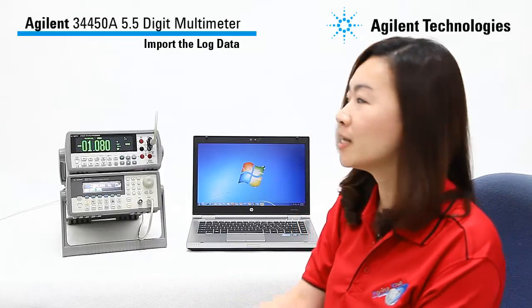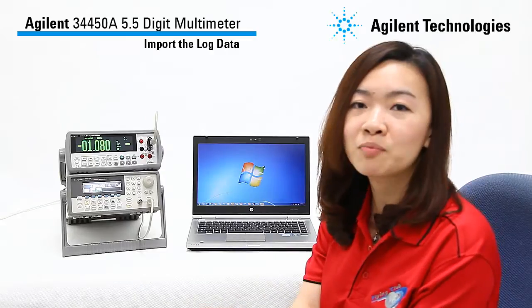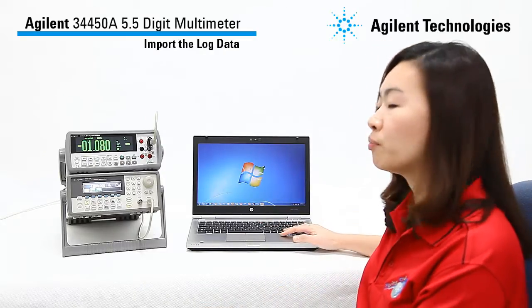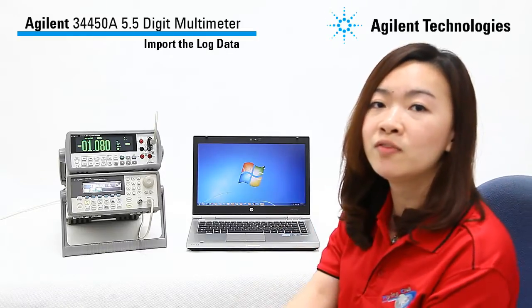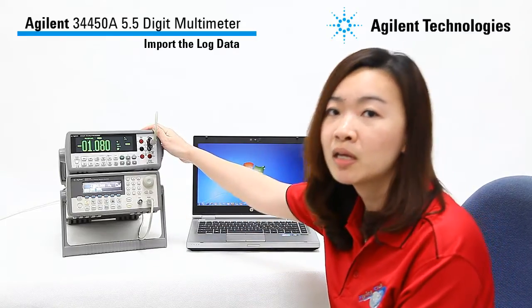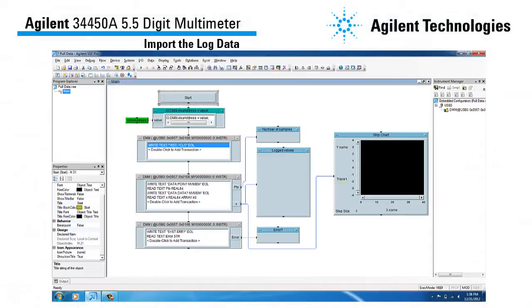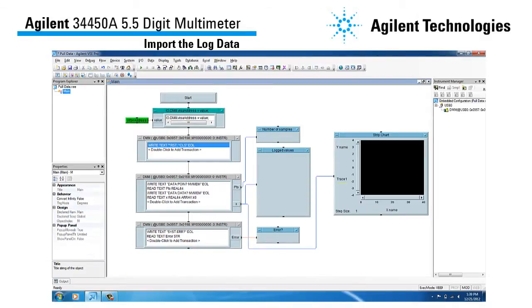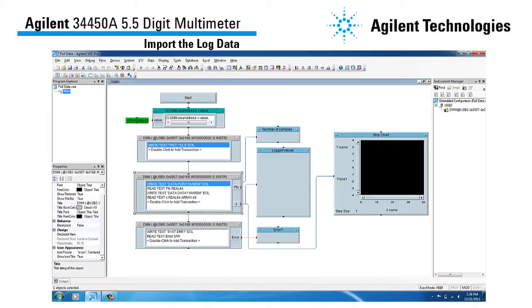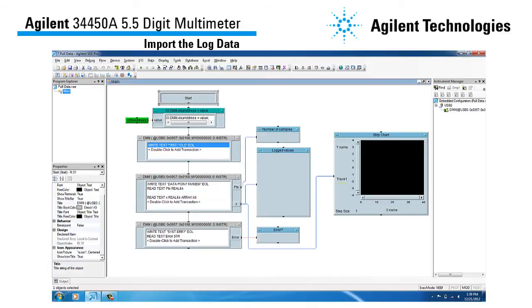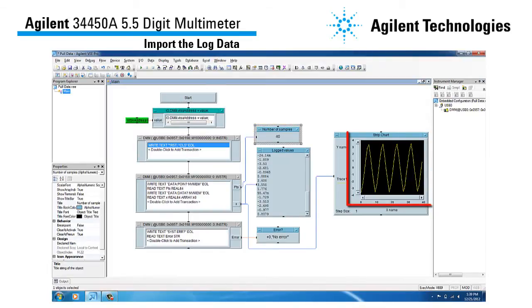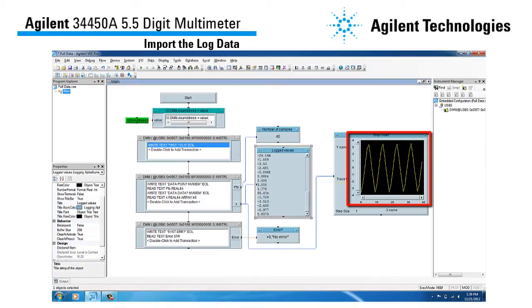So you have learned how to set up the 34450A to perform data logging. Next, you are probably interested in how to import the log data into your computer. Here I have set up a simple program using Agilent VEE Pro to import the log data from the non-volatile memory into my computer. First, I set up the VEE Pro program to recognize my 34450A. Then I use the data points non-volatile memory command to query the number of samples available. Next, I use the data non-volatile memory command to read all the data stored in non-volatile memory to my computer. After running the program, I get the number of samples available and the values — a ramp signal as expected from the 33250A function generator.